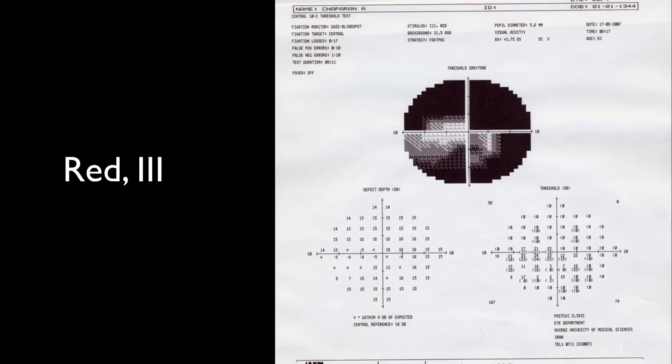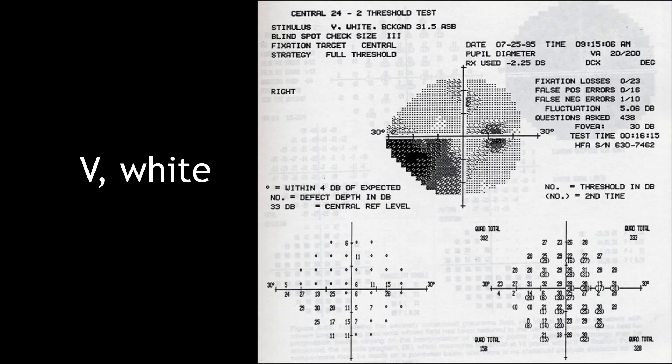There is no database for a red stimulus — even if we choose target size three, we will get a three-in-one printout. The same will happen if we choose stimulus size five even if the color is white, because there is no database for size five, and we get a three-in-one printout.